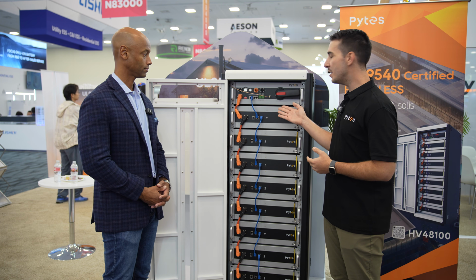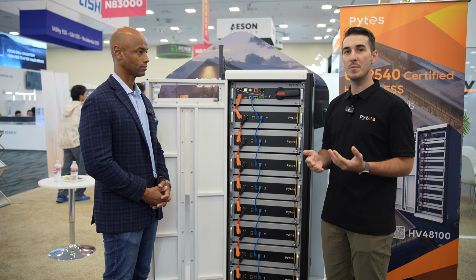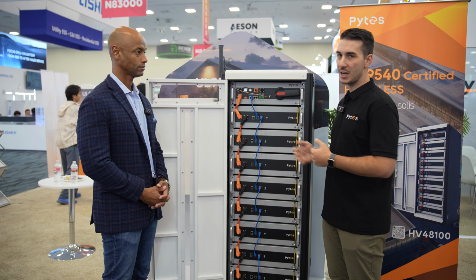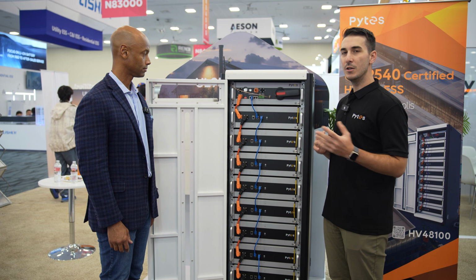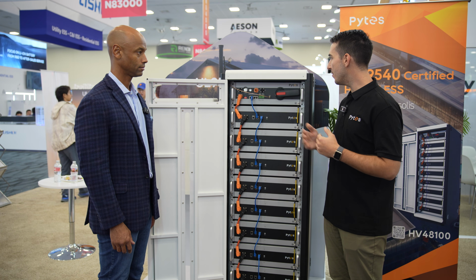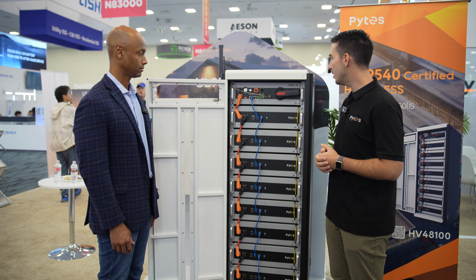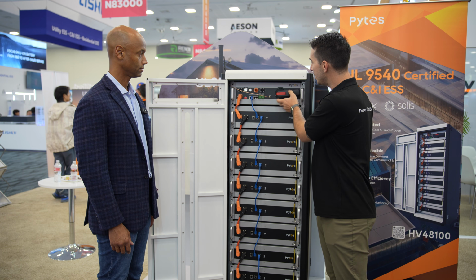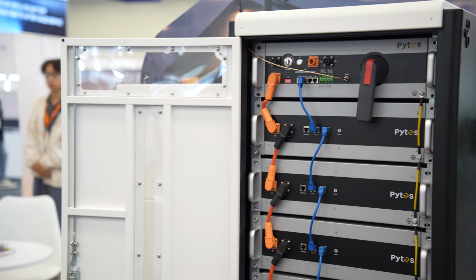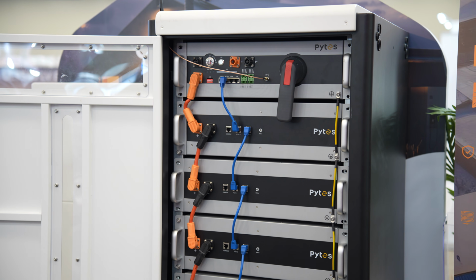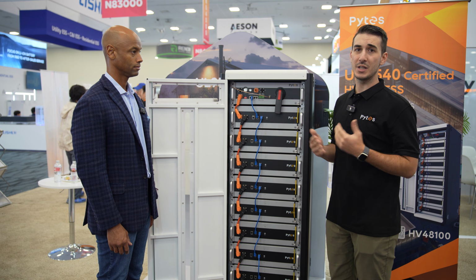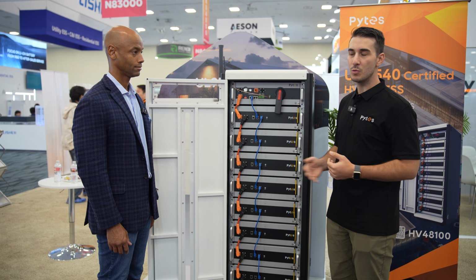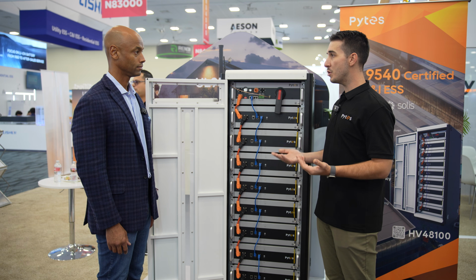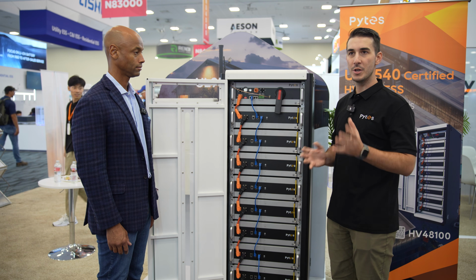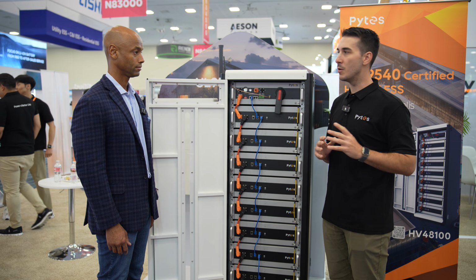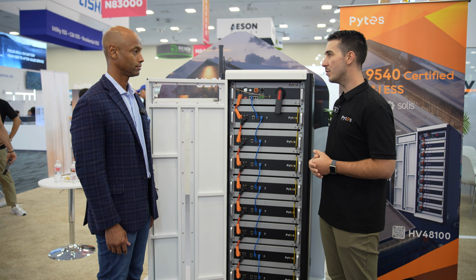In this high voltage model, we've moved away from a MOSFET-based BMS to a contactor-based BMS, which is more robust and safer in general. You now have physical disconnection between the control unit and the rest of the battery modules. This installer contactor switch will physically disconnect both the positive and negative poles on the battery unit. Since this is a contactor-based BMS, we can now also do a remote shutdown of the system. This model also has a pre-charge circuit incorporated, hoping to avoid potential damage or BMS board issues when starting up an inverter for the first time.